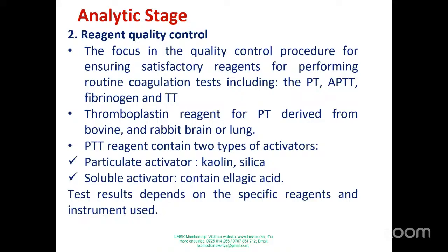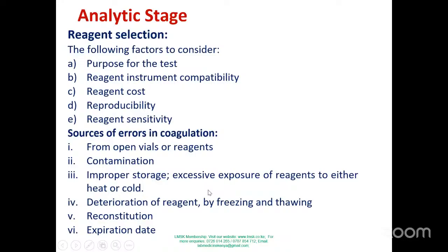And for the PT, as we have said, it's very important. Don't ever forget, once you've received that reagent, you check the ISI that has been given by the manufacturer and configure that in your system for correct result interpretation. So the test results will depend on the specific reagents and instrument used. Reagent selection, the purpose of the test will guide you. The instrument compatibility will guide you. For example, which instrument are you using at your place?